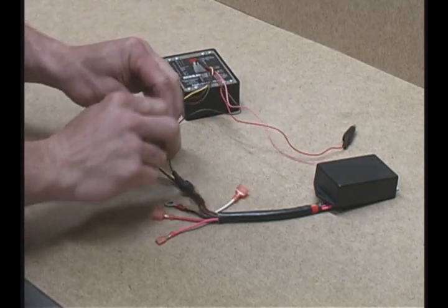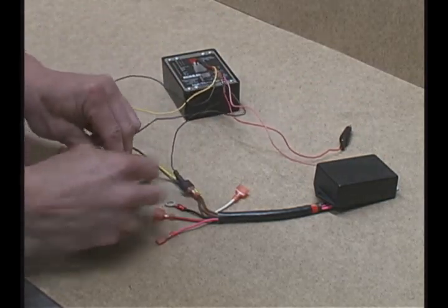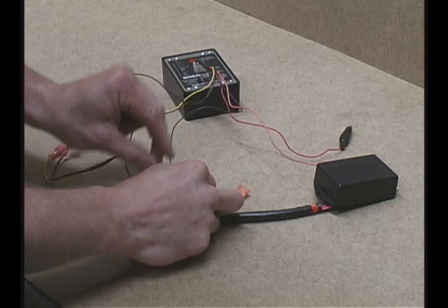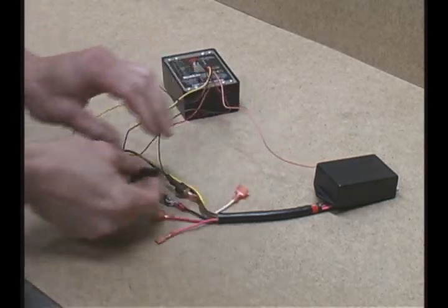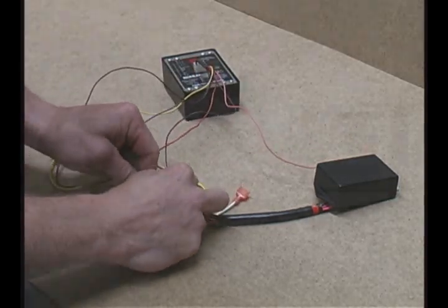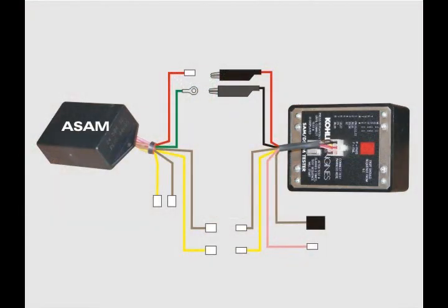Use care when connecting test leads to an ASAM that has a set of long yellow and brown leads and a set of short yellow and brown leads. Each pair will be tested separately. Connect the tester as follows. Yellow tester lead to the long yellow module lead, the brown tester lead to the long brown module lead, and the red tester lead to the red module lead. Finally, connect the black tester lead to the green or black module ground lead. The pink tester lead and the brown tester lead with black terminal end are not used when testing an ASAM.